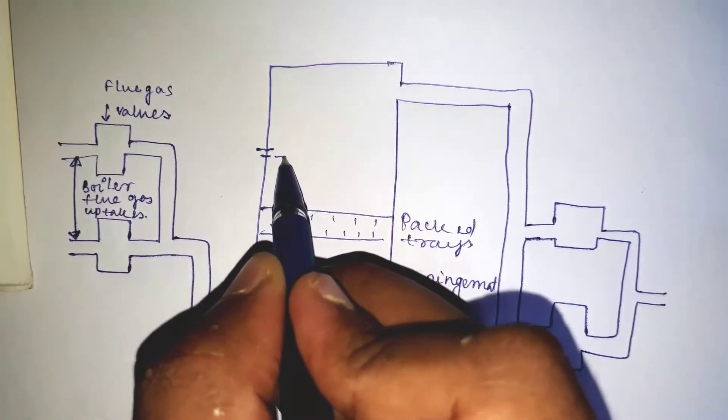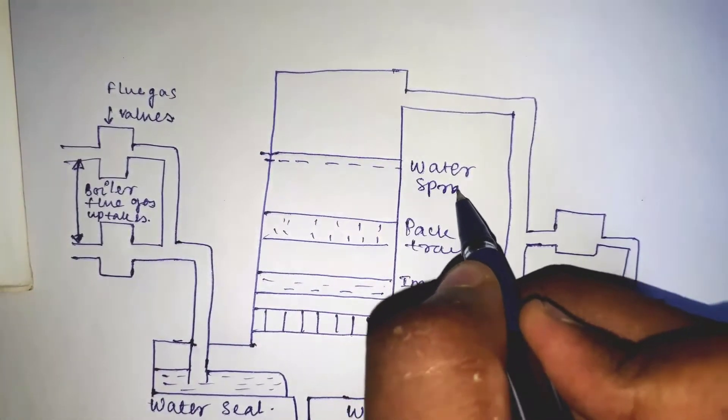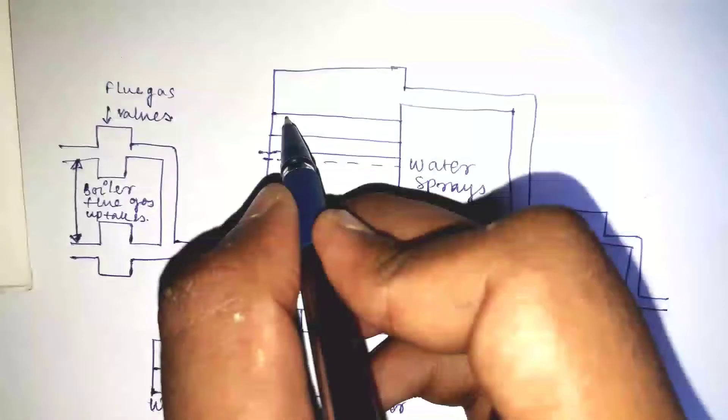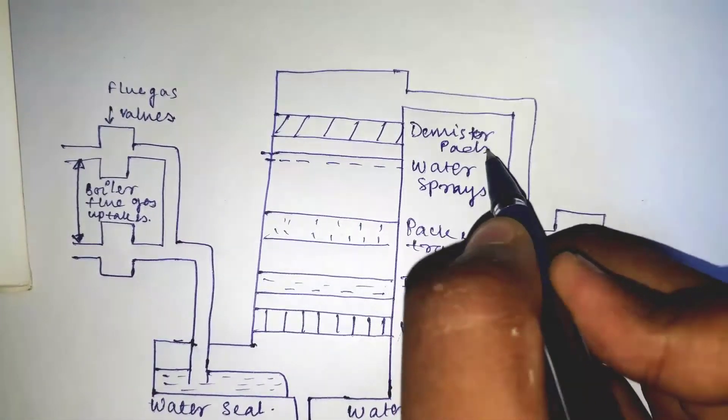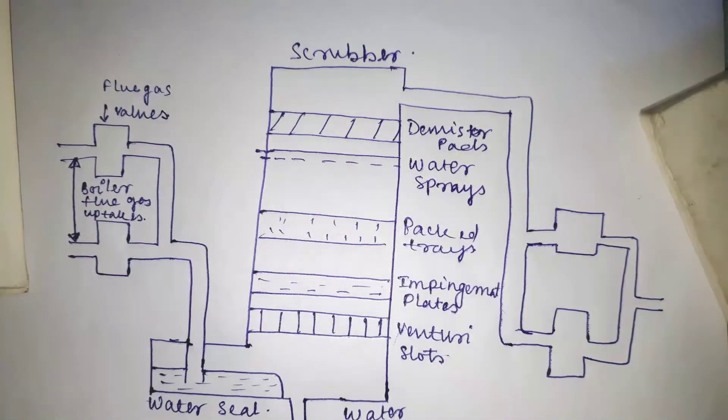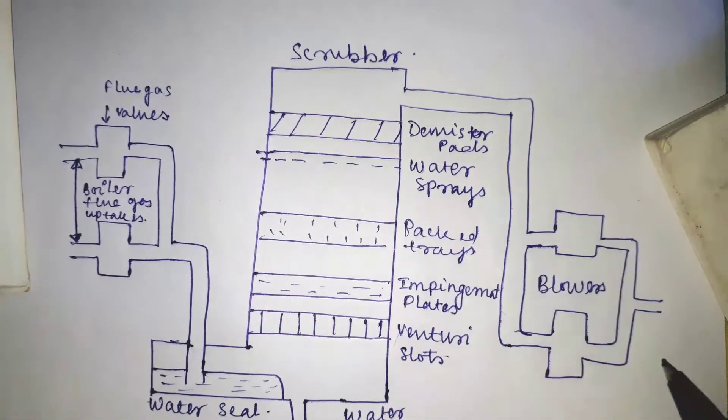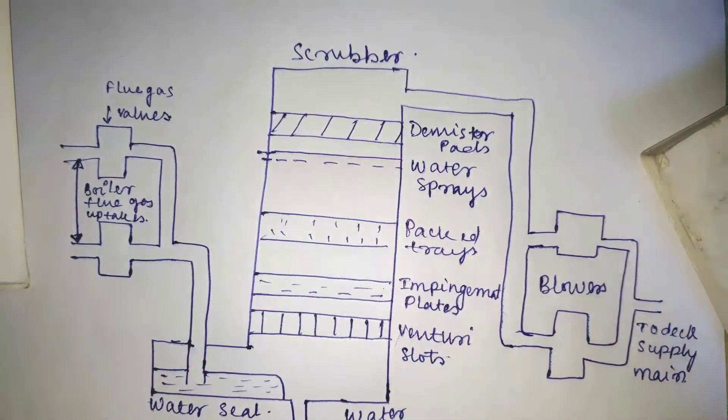Scrubber. The scrubber has a threefold purpose: first, to cool the flue gas; second, to remove most of the sulfur dioxide; third, to remove most of the soot particles. The design of the scrubber varies considerably, but in all scrubbers, flue gas is brought into contact with large quantities of sea water by which the gas is cooled and cleaned.